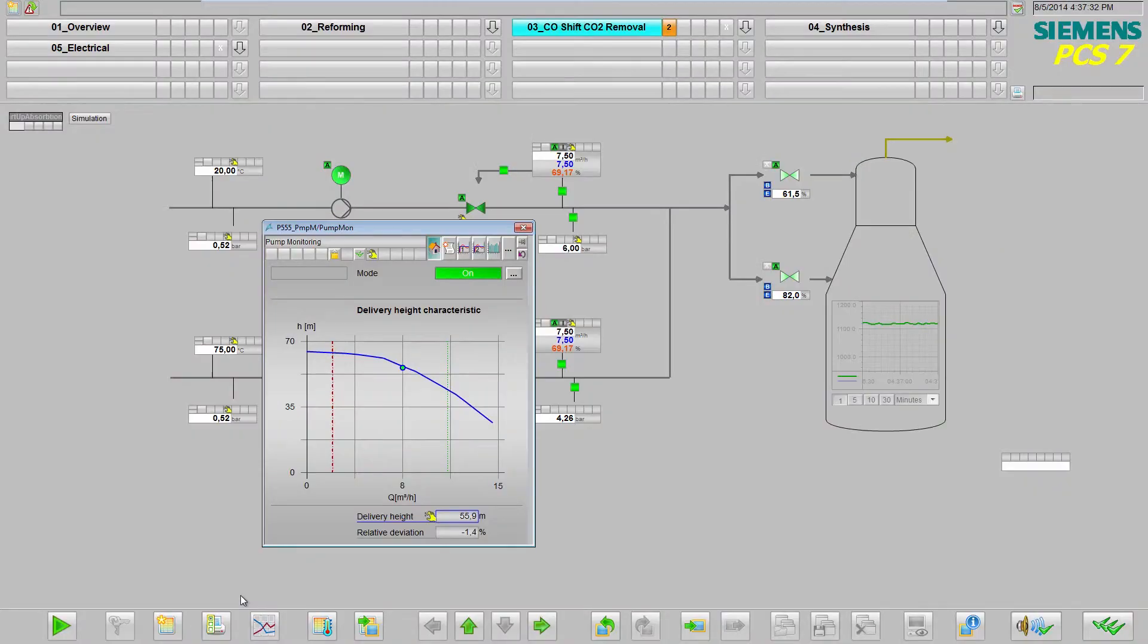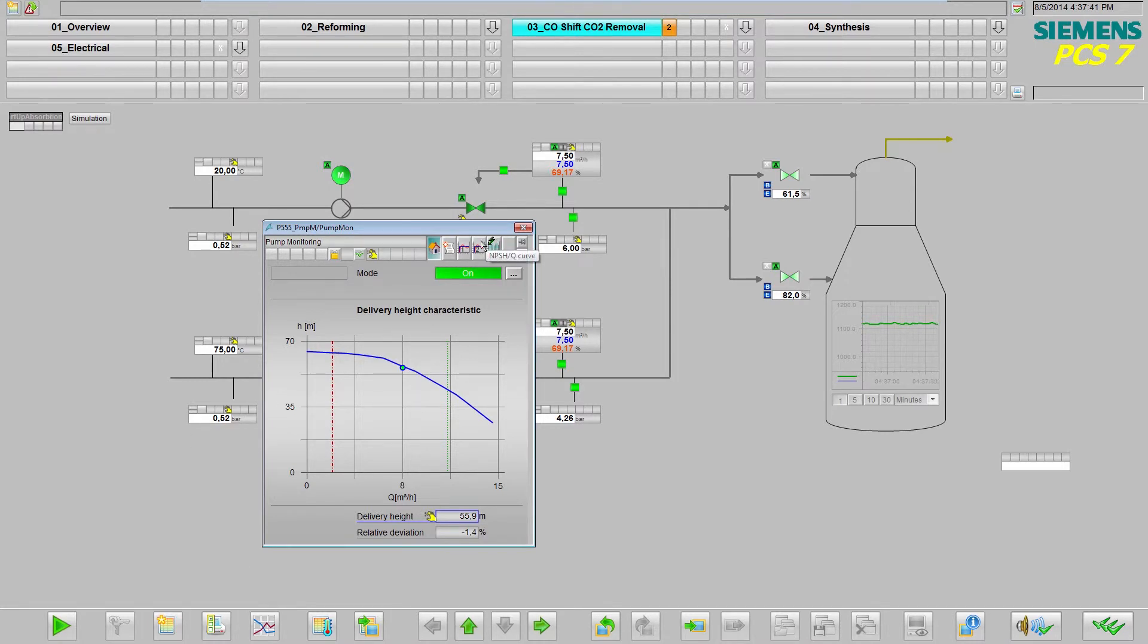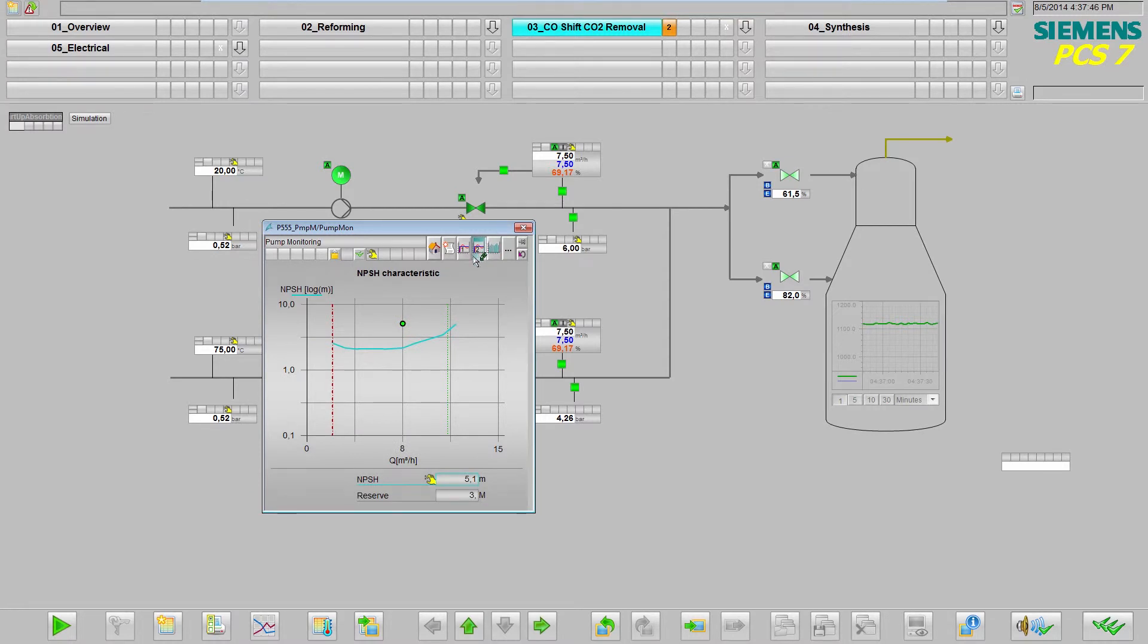In order to detect cavitation, the monitoring system calculates the NPSH value and displays this in another view of the pump monitoring faceplate. In this case, the working point must be above the characteristic curve, because for the pump, the dangerous cavitation range is below this.